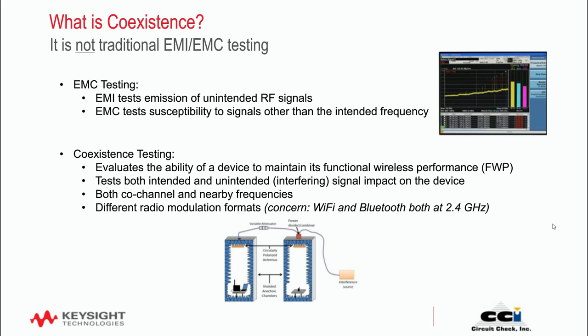It tests both the intended and unintended signals for what impact they'll have on the device. So when the device is transmitting on the air, is it working properly? Is the throughput all right? What happens if some signal in the same vicinity—either on the same frequency, the same band, the same channel, or even adjacent channels—comes up? What impact does that have on the functional performance of that device? Again, it tests both co-channel and other nearby frequencies.